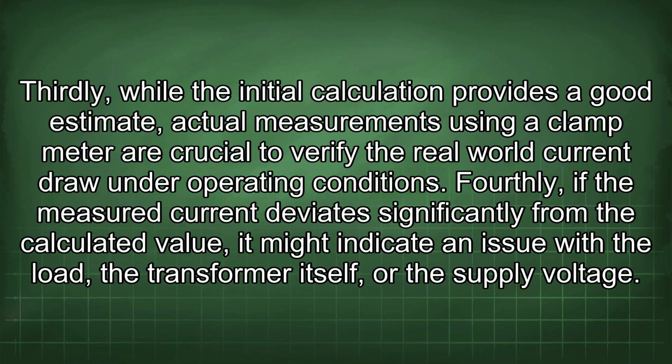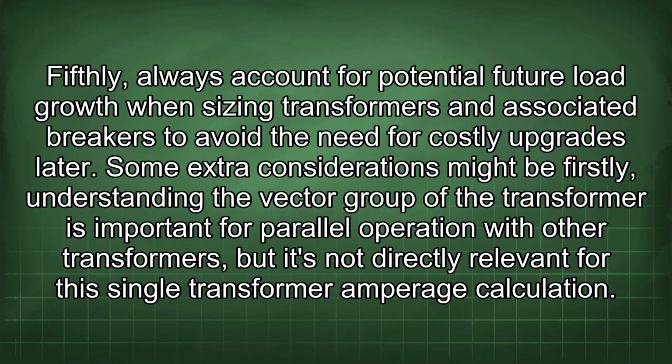Fourthly, if the measured current deviates significantly from the calculated value, it might indicate an issue with the load, the transformer itself, or the supply voltage. Fifthly, always account for potential future load growth when sizing transformers and associated breakers to avoid the need for costly upgrades later. Some extra considerations might be: firstly, understanding the vector group of the transformer is important for parallel operation with other transformers, but it's not directly relevant for the single transformer amperage calculation.